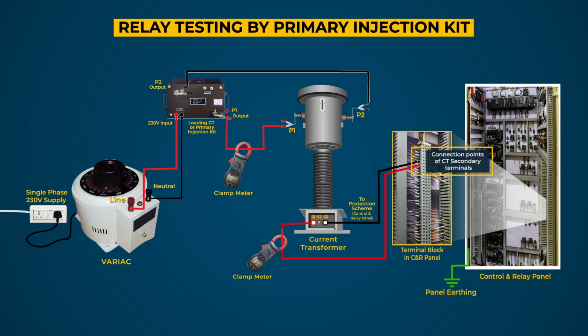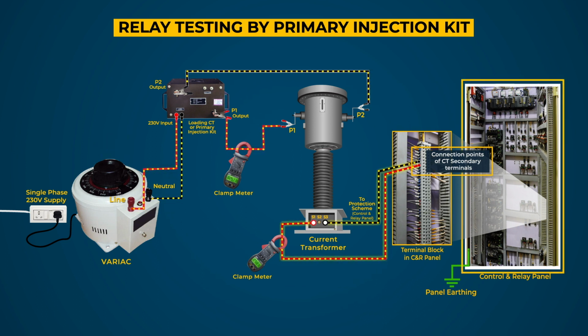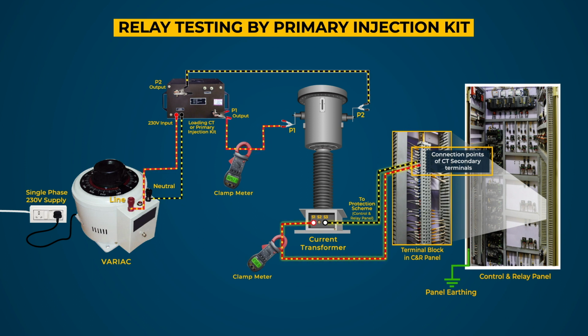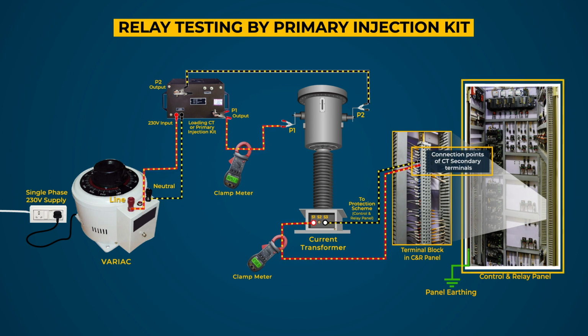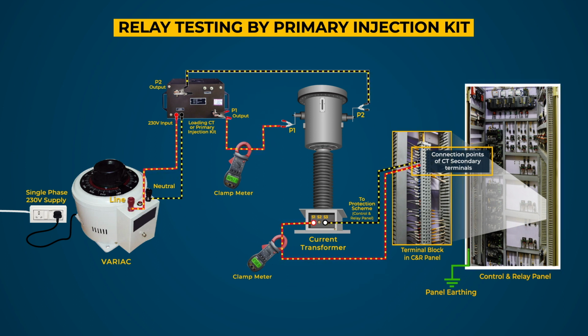Now inject the current in the primary, increase gradually up to setting current of protection scheme, and check on control and relay panel whether the protection scheme is operated or not. If protection scheme operates as per setting current of relay, then the relay is working fine, otherwise check the issues. Check the operation of all the relays using this method.